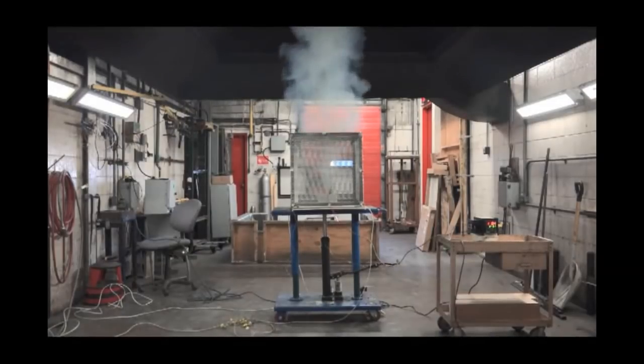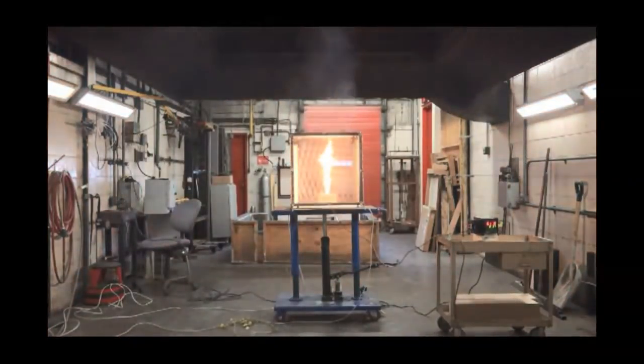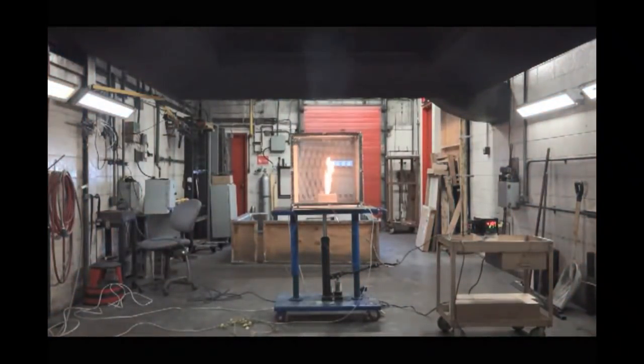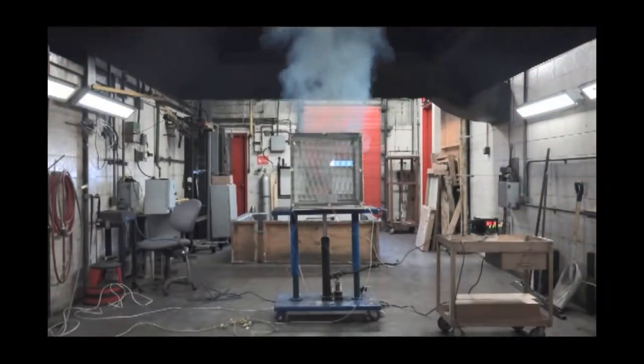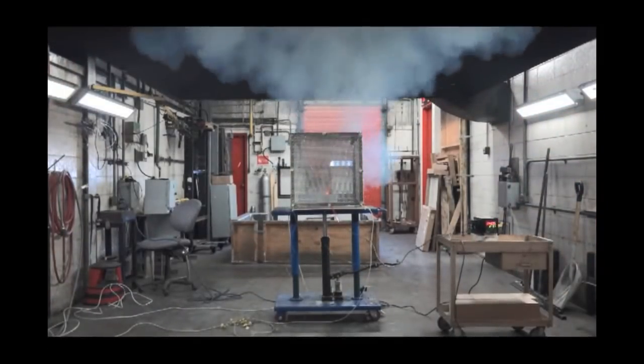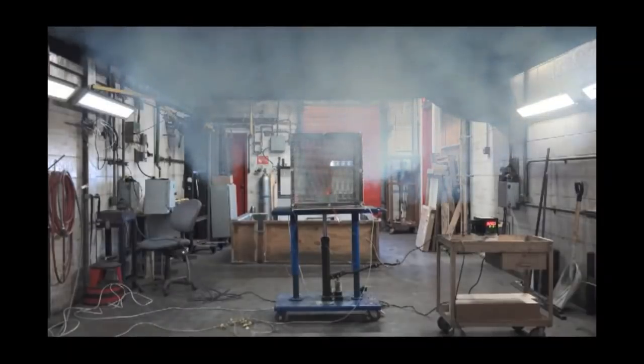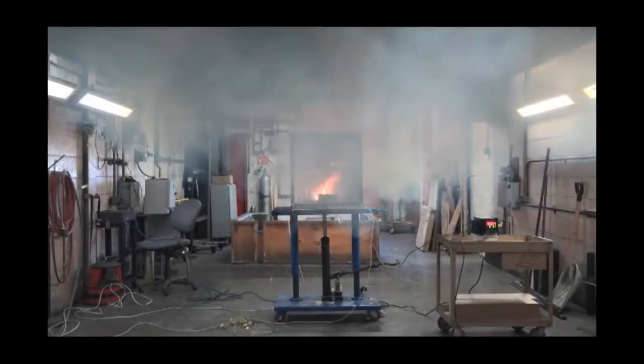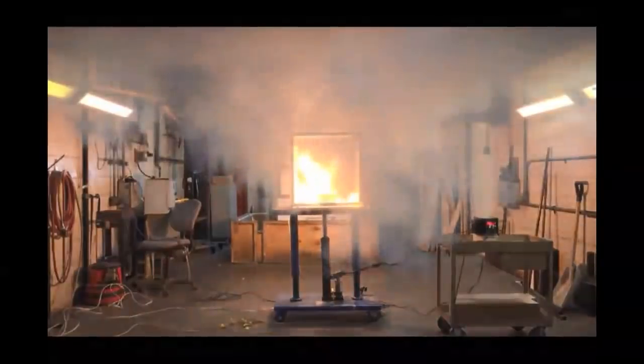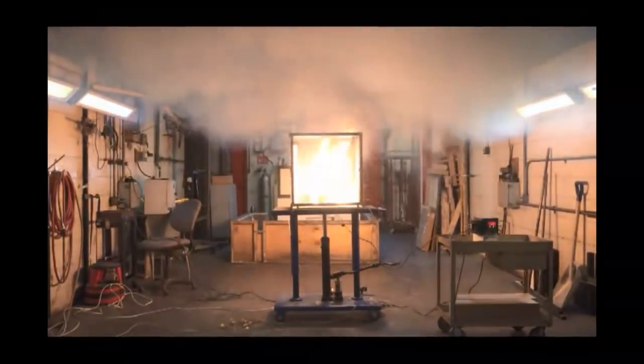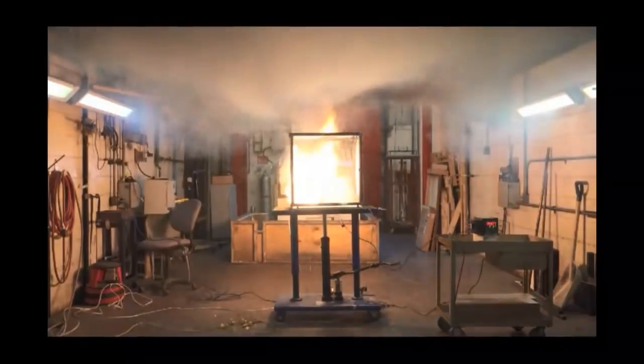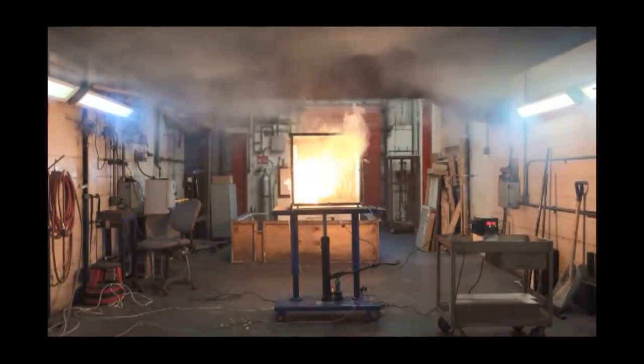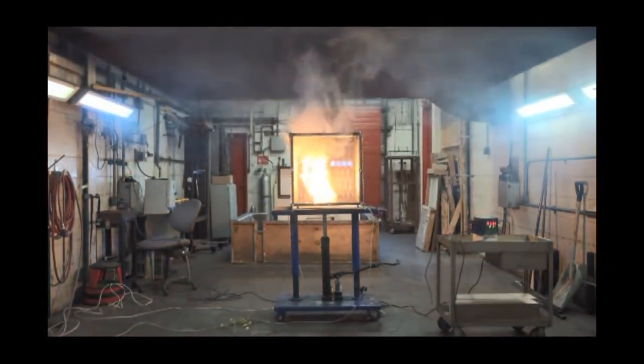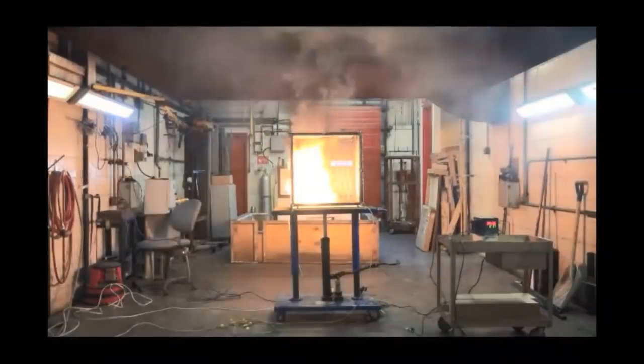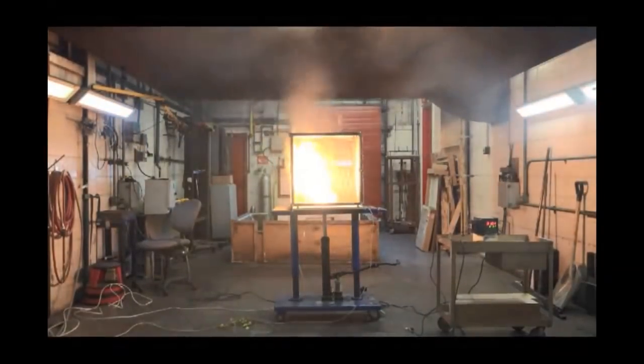We're using an external heating mechanism, just an external heating coil, to start to increase the internal temperature of the battery and force it into failure. I think in subsequent testing, we're probably going to take that combustible chair out of the lab so we don't put that at risk. But you can see the transition here into a significant amount of flaming, and also a significant amount of off-gassing. We're under the cone calorimeter, so we are evacuating that smoke out of that room.